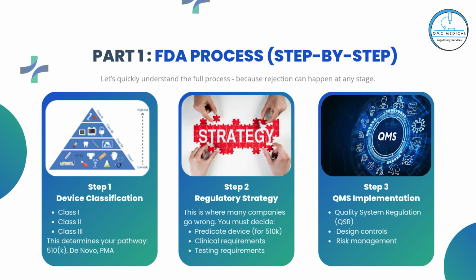Part 1. FDA process, step-by-step. Let's quickly understand the full process because rejection can happen at any stage. Step 1. Device classification. Class 1, Class 2, Class 3. This determines your pathway: 510K, De Novo, PMA. Step 2. Regulatory strategy. This is where many companies go wrong. You must decide predicate device for 510K, clinical requirements, testing requirements. Step 3. QMS implementation. Quality System Regulation, QSR, design controls, risk management.